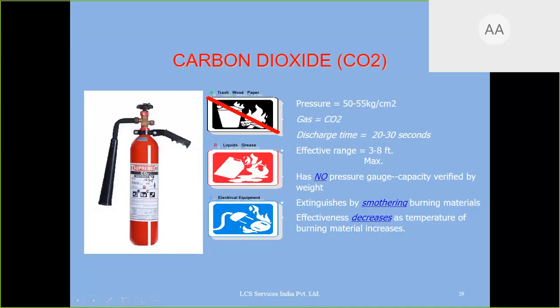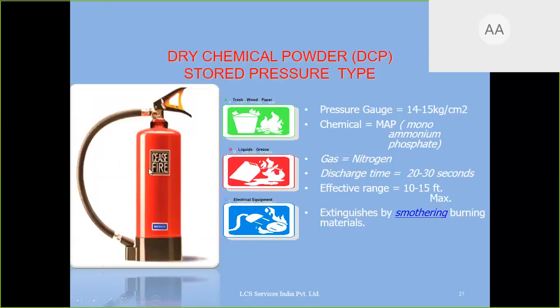Because the pressure is so high, I cannot hold a pressure gauge at this temperature. You have to check whether CO2 is there or not by weight, and it controls the fire by the smothering method. Effectiveness decreases if the temperature of the fire goes high. So it cannot be used in A class, it can be used for B class or C class. Whereas this extinguisher, here it is written somewhere, you will find ABC. This extinguisher can be used for A class fire, B class fire, or C class fire.